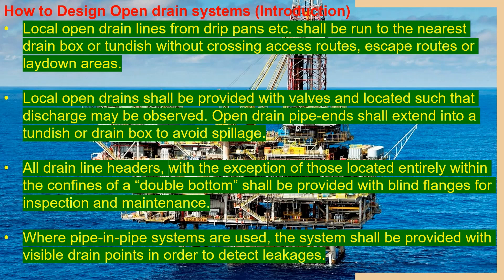Open drain pipe ends shall extend into a tundish or drain box to avoid spillage. All drain lines, with the exception of those located within the confines of a double bottom, shall be provided with blind flanges for inspection and maintenance. Where pipe-in-pipe systems are used, the system shall be provided with visible drain points in order to detect leakage.